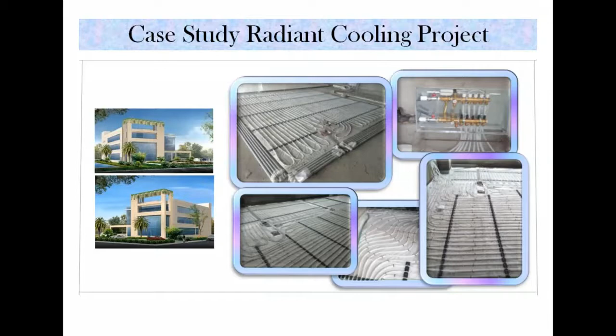Now as in this case study, the sensible load is something like 123.2 TR, while the latent load is 41. This is based on the heat load calculations we had done. And based on the sensible load, we have worked out the air quantity of 58,280. Now, depending upon what is the area available for me to do the radiant cooling, say if it's the underfloor and the ceiling, based on that, say if it is 100 square feet or 100 square meter.